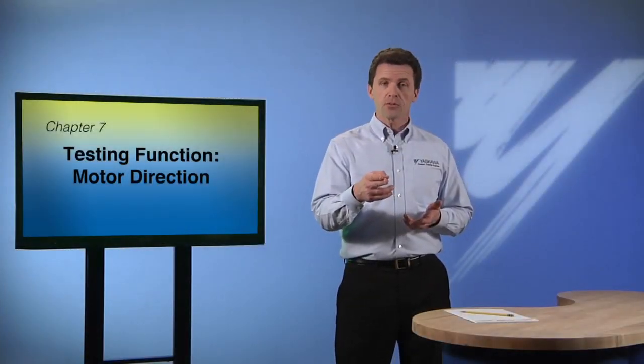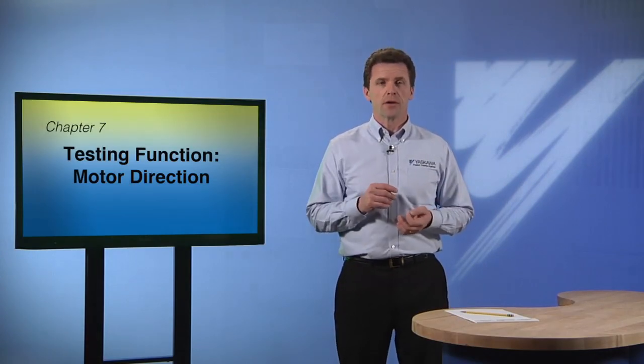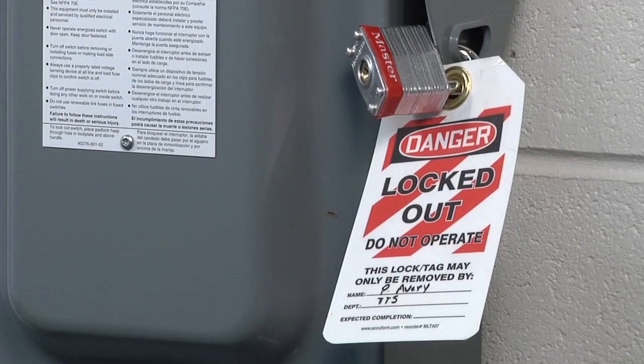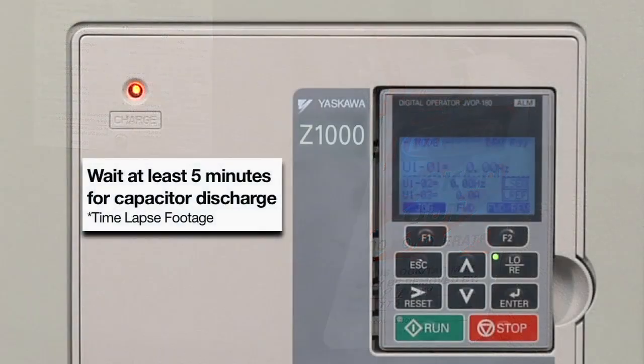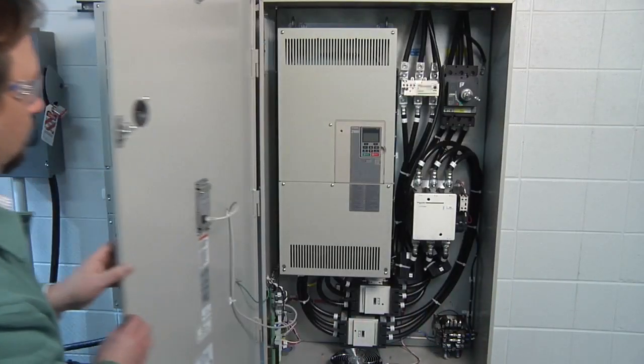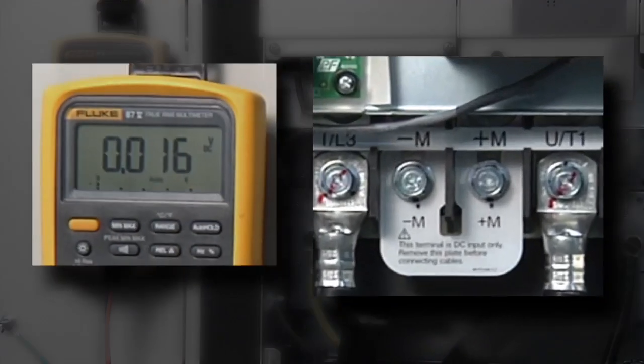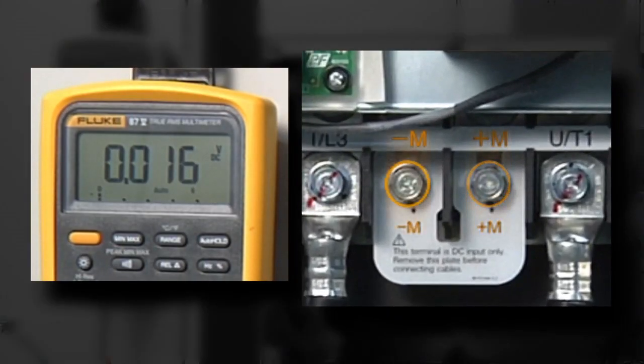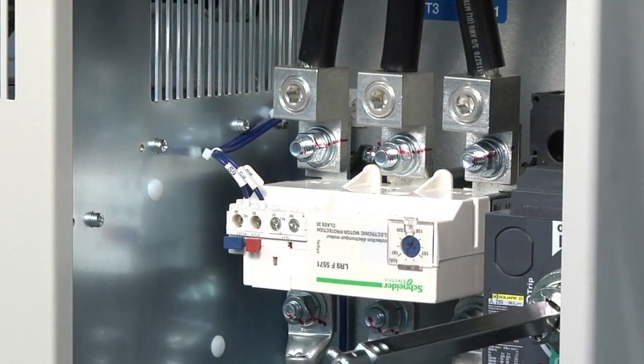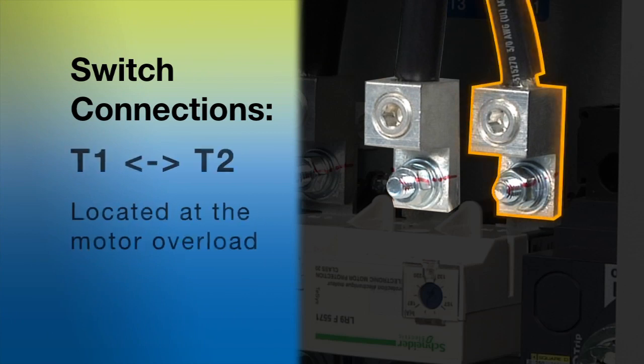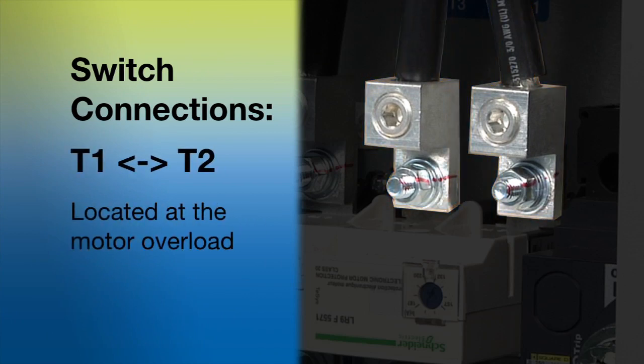If the motor is rotating in the wrong direction, the solution is a simple one. Shut down power, lockout and tagout, making sure that you wait 5 minutes after lockout before going on to the next step, so you're sure that power in the drive's capacitor is discharged. Then open the enclosure. Check the DC bus on the drive at M+ and M- to make sure that the bus voltage is below 10 volts DC. You're now ready to switch connections T1 and T2 at the motor overload. That should reverse the motor's direction.